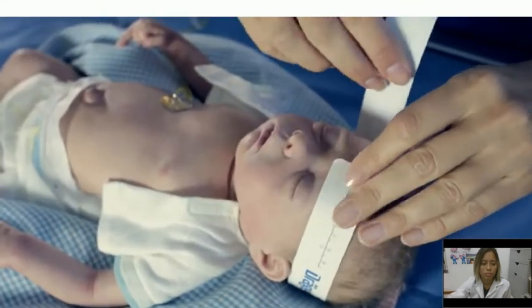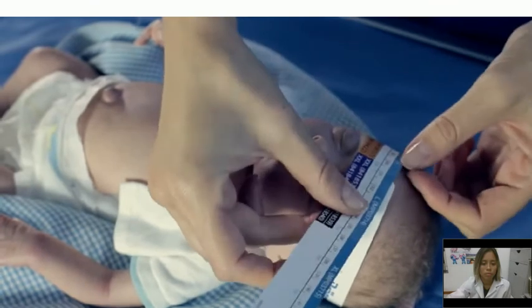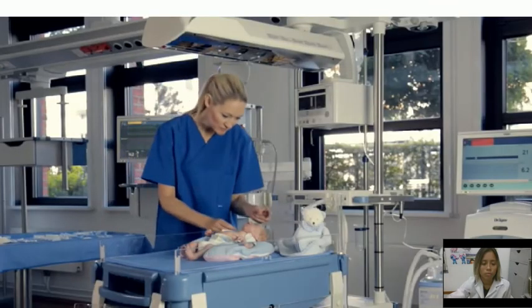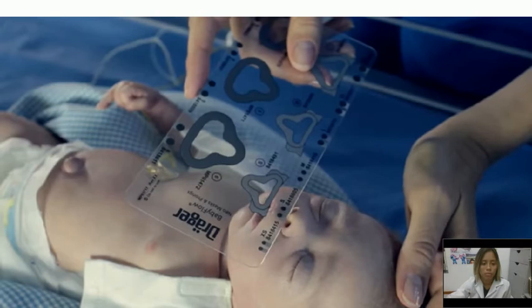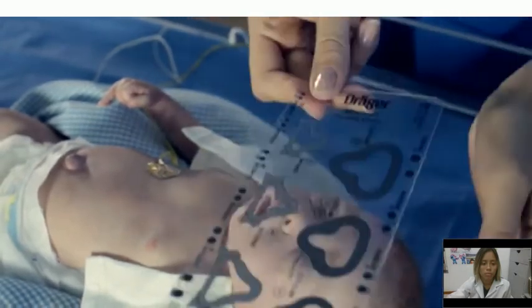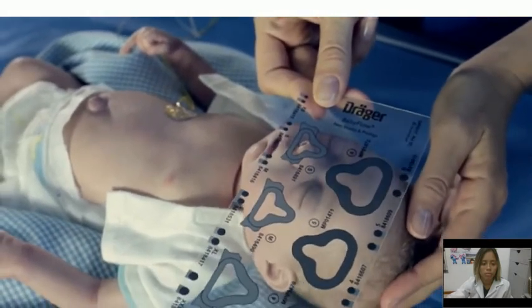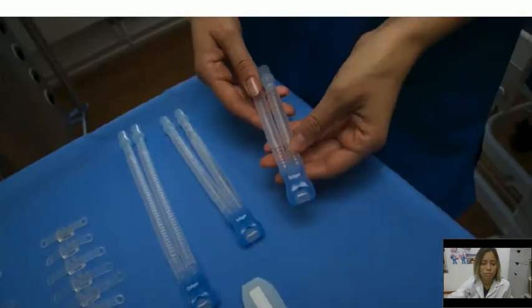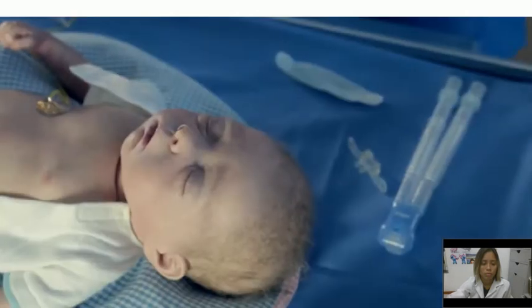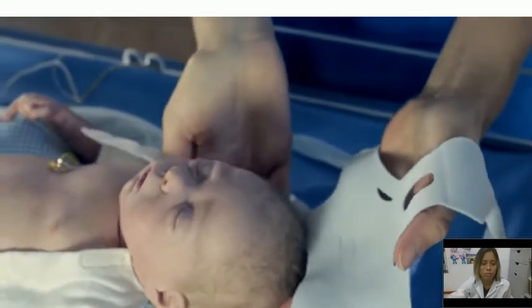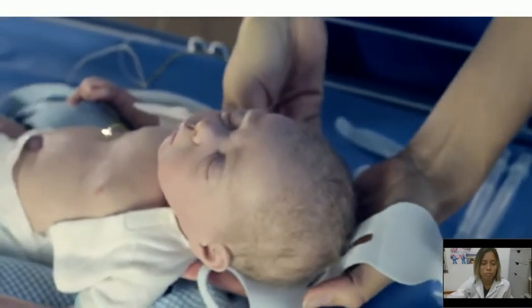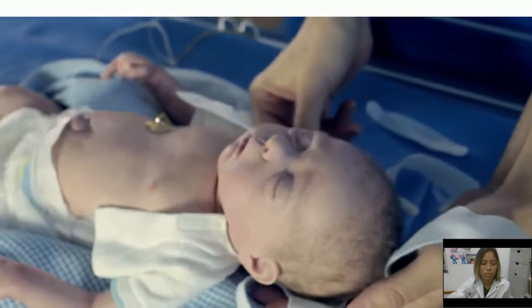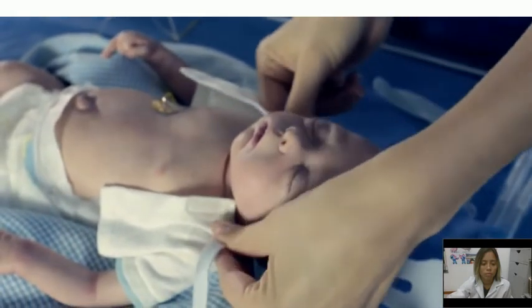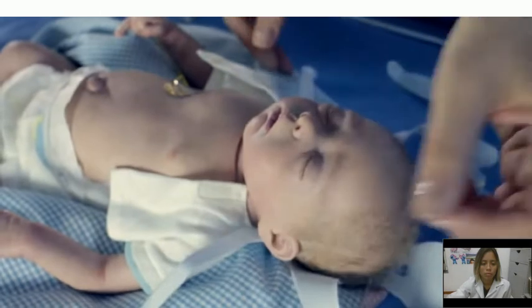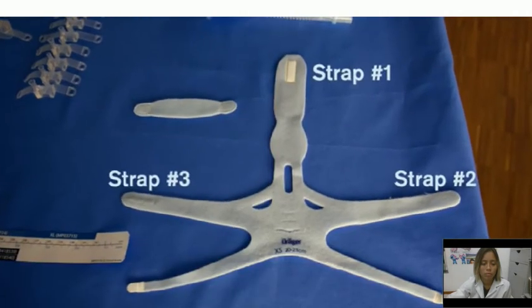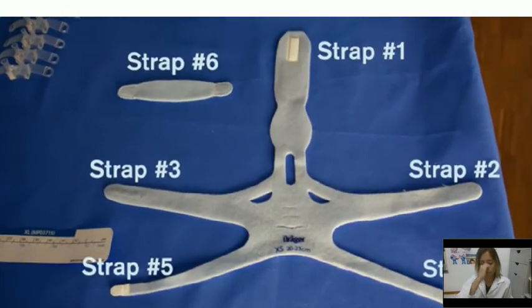Start by using the measurement tape to check the head circumference of the patient and the sizing card to identify the appropriate prong size. Based on these measurements, choose the best fit headgear and prong option for the infant. Then choose the best BabyFlow Plus length out of the 3 offerings. Gently lift the patient's head and position the headgear underneath. Ensure that the headgear is centered and positioned directly on the hairline. For best positioning, avoid wrinkling the material. Notice the headgear is labeled with numbers to help assist you in securing the accessory correctly.